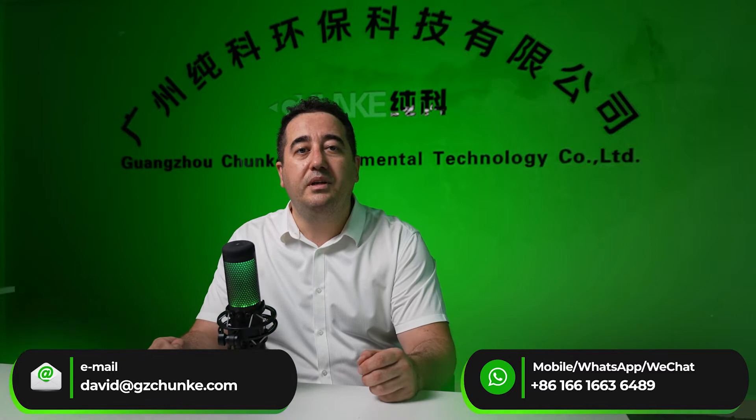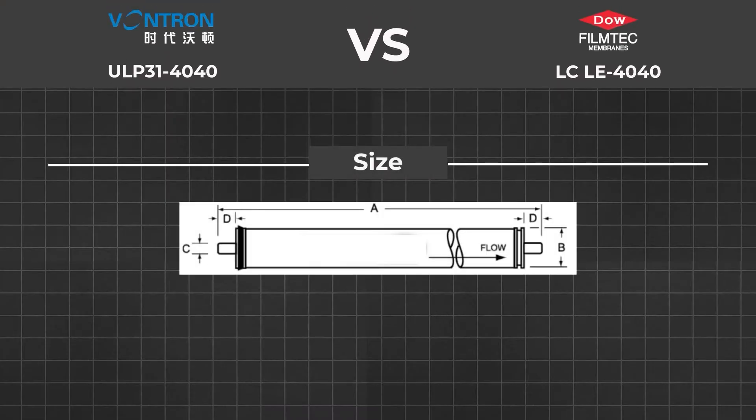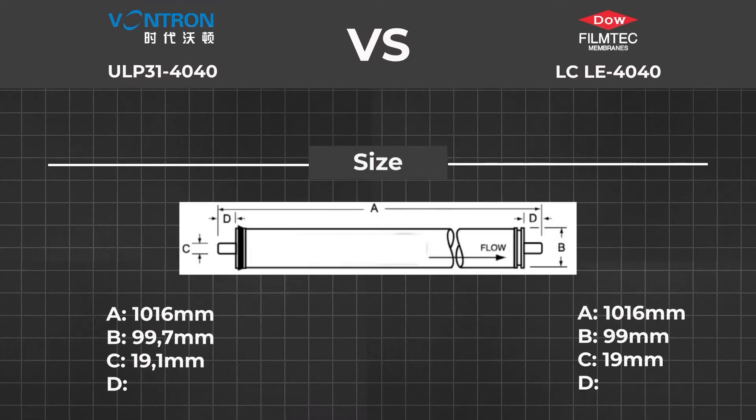First of all, we start comparing features of these two membranes from their official web page. We got the specification and now we check together. Size: you can see from the drawing, both membranes have the same length of 1016mm, but the diameter of Vontron is a little bigger than FilmTec.